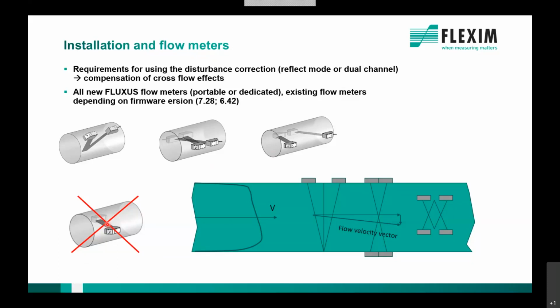If you want to install it like that, the flow meter will basically tell you it cannot be used. You have to go on without the disturbance correction. Where is it available? We introduced that product last year, and for all new products, all products you just bought or purchased from us, it's available. If you want to know if it's really available, look at the firmware version. If it's a new platform, it's 7.28. If it's an old platform, like the portable meter, it's a 6.42 firmware version.